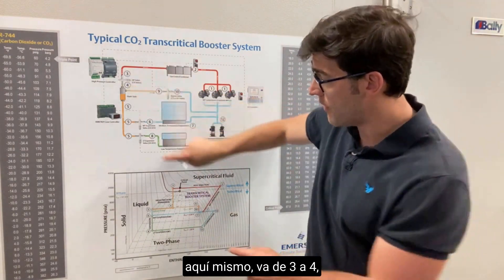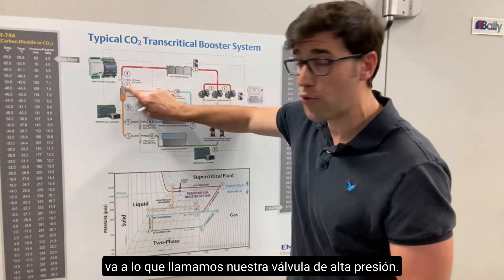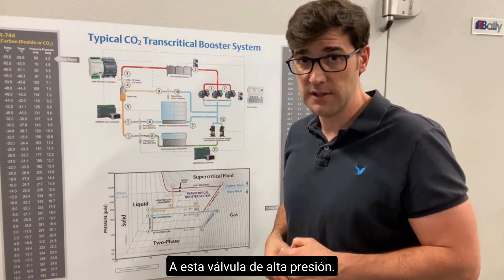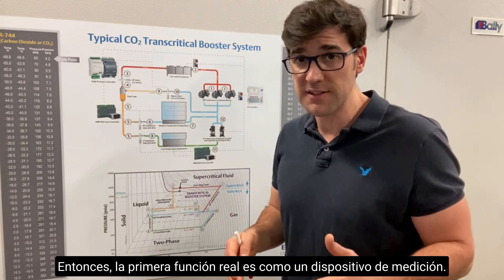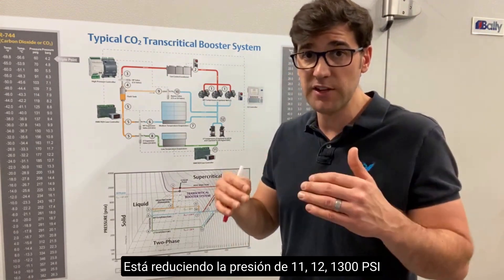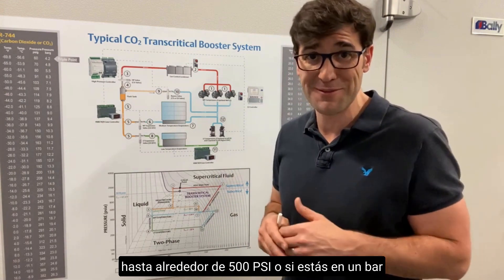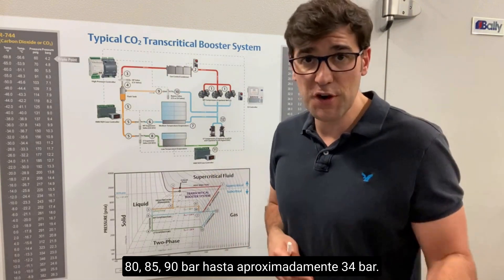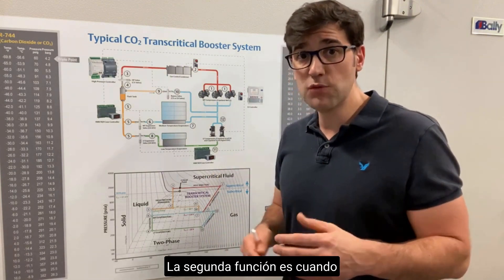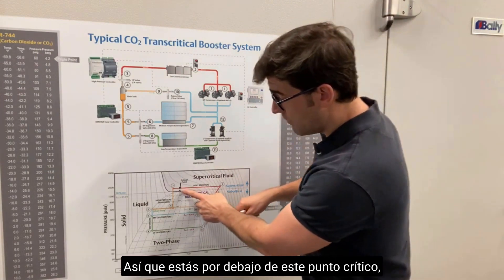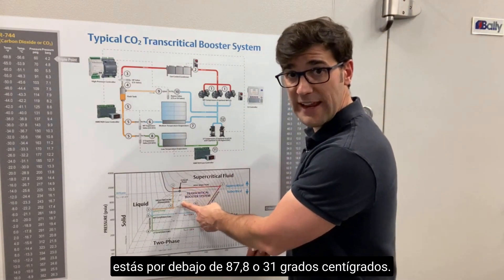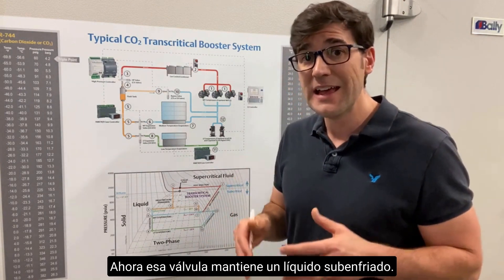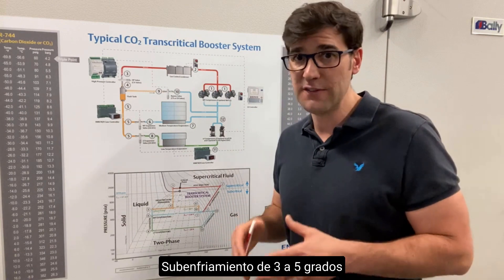Out of the gas cooler, from three to four, we go to what we call our high pressure valve, which has three main functions. The first function is as a metering device — it reduces pressure from 1100–1300 psi down to about 500 psi, or from 80–90 bar down to about 34 bar. The second function applies when you're in the subcritical zone, below 87.8°F or 31°C — the valve maintains a subcooled liquid with 3 to 5 degrees of subcooling.